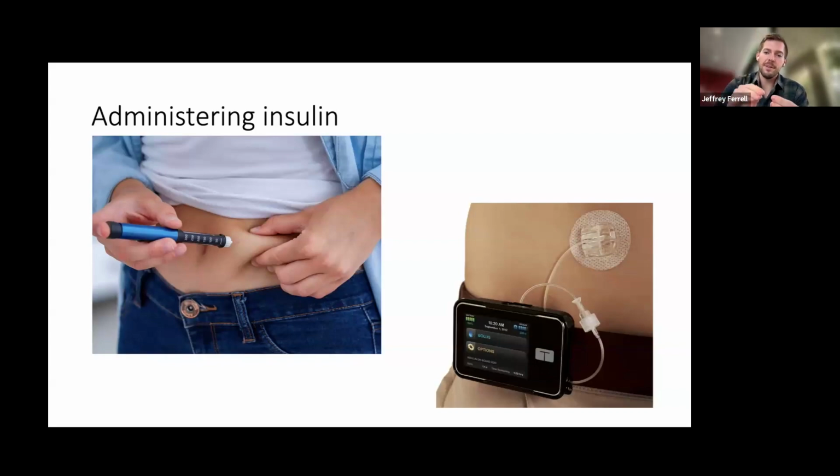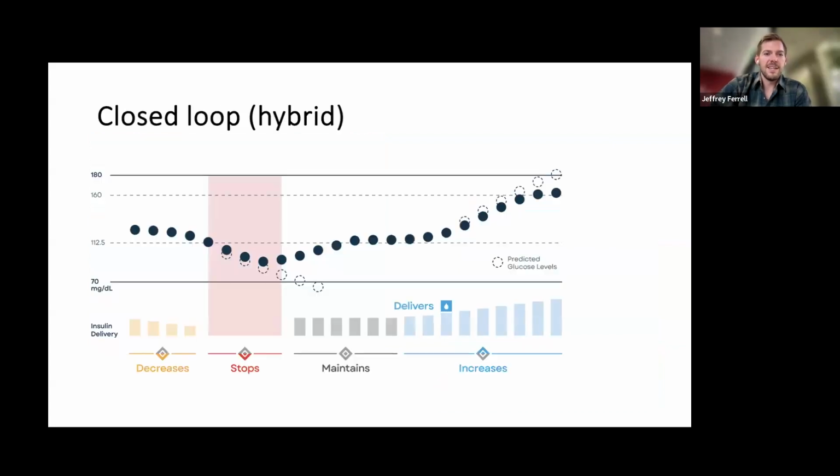So it uses a needle to put this device on the skin, and then the needle retracts and it leaves that cannula there. So we can infuse insulin into that subcutaneous space right underneath the skin and give insulin into the fat there. You would change the locations every once in a while, but that pump, you can essentially tell it how much insulin you'd like to give. There's a reservoir of insulin inside the pump, and it uses the tubing to get the insulin underneath the skin. Quite effective devices.